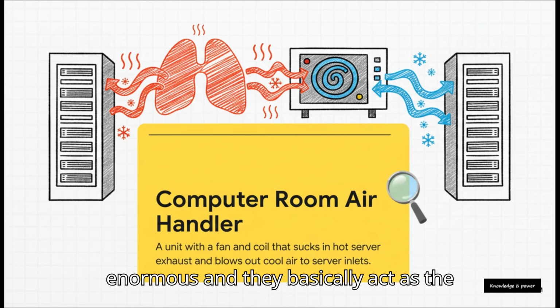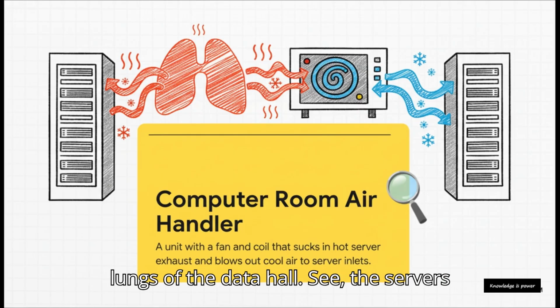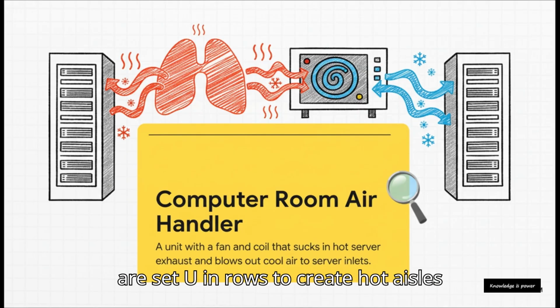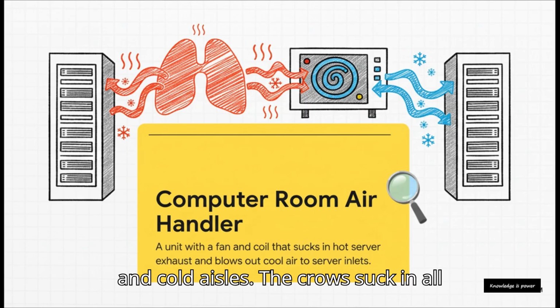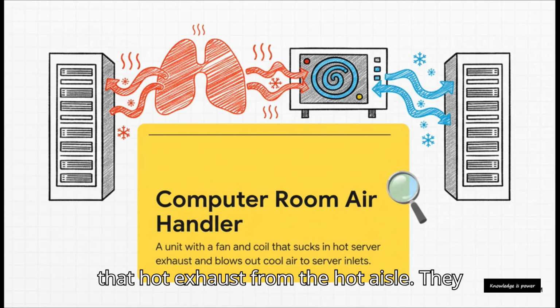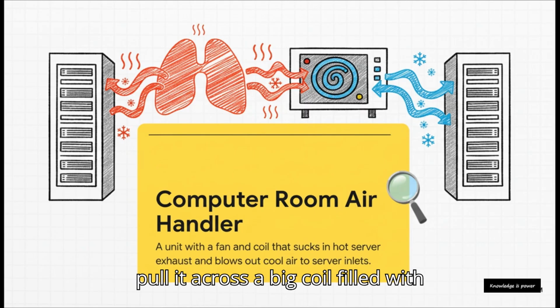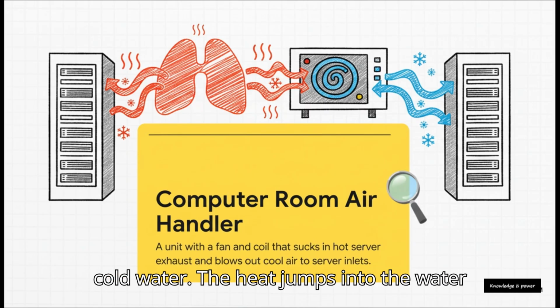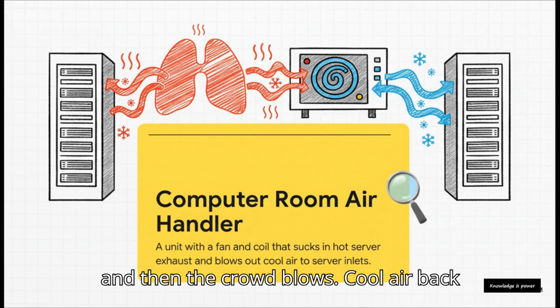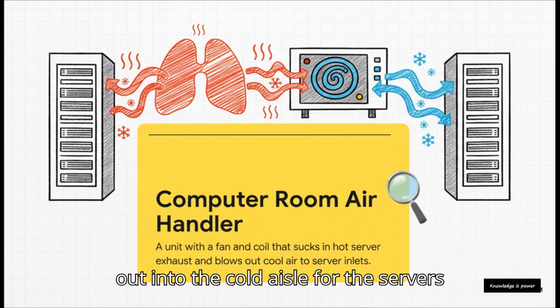These things are absolutely enormous, and they basically act as the lungs of the data hall. The servers are set up in rows to create hot aisles and cold aisles. The CRAHs suck in all that hot exhaust from the hot aisle, pull it across a big coil filled with cold water, the heat jumps into the water, and then the CRAH blows cool air back out into the cold aisle for the servers to breathe in.